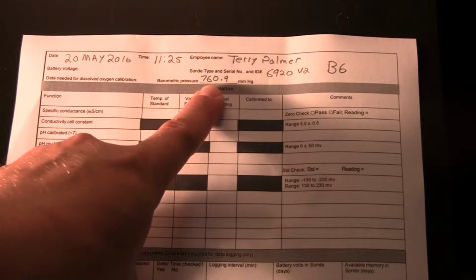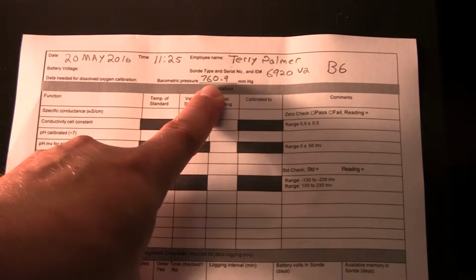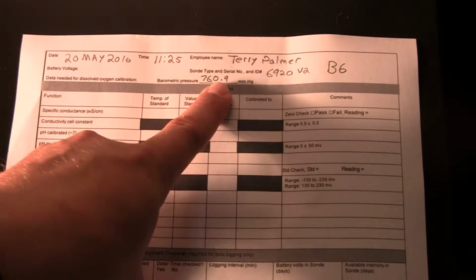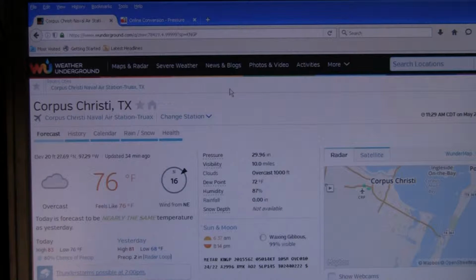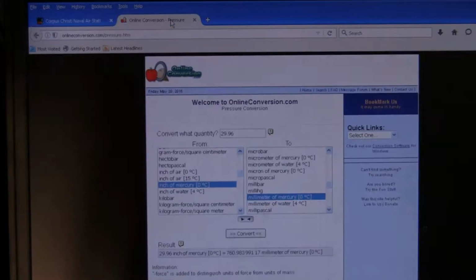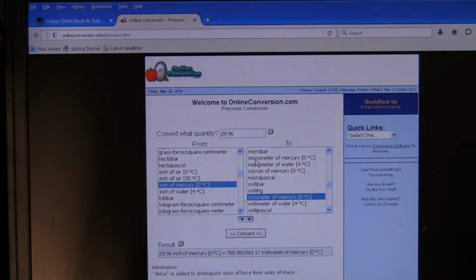Also, we have the barometric pressure, so I'll demonstrate to you how to locate the barometric pressure to give a lab reading. To verify pressure of the Sonde unit, navigate the computer to Weather Underground and go to Corpus Christi Naval Air Station site, which is the nearest to A&M Corpus. Right now the pressure is 29.96 inches. Then you'll need to convert that into millimeters of mercury. So using this website, I'm able to convert it from inches of mercury to millimeters of mercury. So right now the pressure is 760.9, and write that down on the calibration sheet.